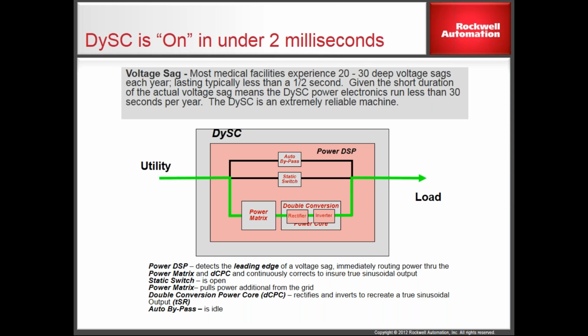The limit is I can only do this for 5 seconds because I'm doubling current, and if I went longer than that, I would violate the IEEE standards on the wires and the breakers that are feeding the system. Right? So to stay within the IEEE standards, the 5 seconds is a limit. So all the DySCs that we have, little ones to great big ones, all work exactly the same way, all have the same capabilities and limitations. They can deal with this problem for up to 5 seconds.